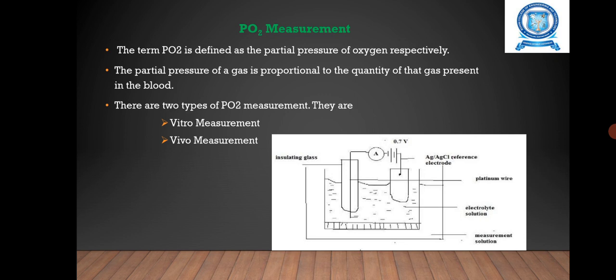If PO2 is increased, it is usually the result of excessive oxygen administration that needs to be adjusted downwards. If PO2 is decreased, it results from any number of respiratory or cardiopulmonary problems. The PO2 electrode system uses principles similar to those for pH measurement. This voltage attracts oxygen molecules to the cathode surface where they react with water.